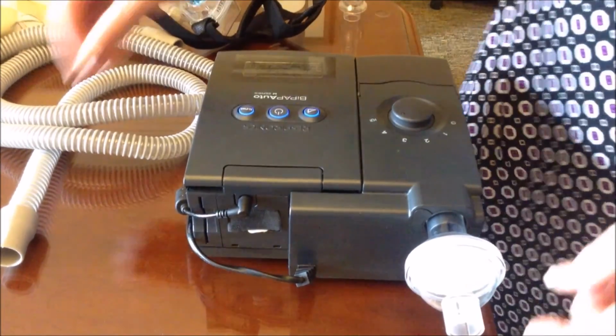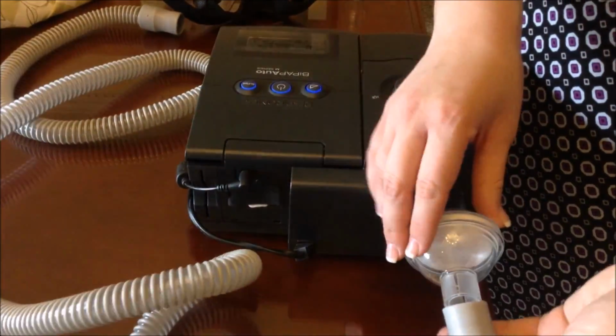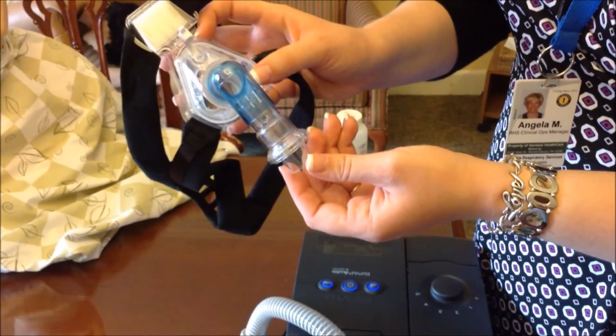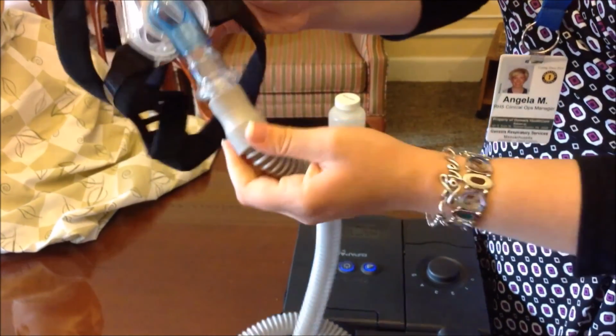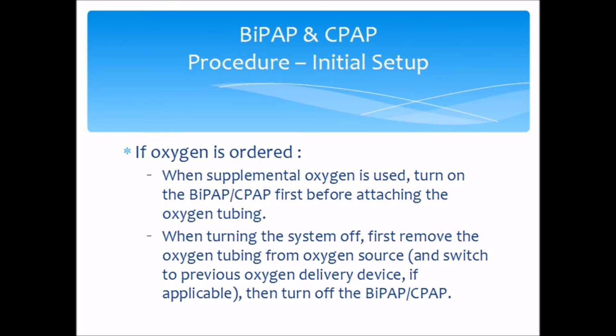Connect the end of the large bore tubing to the outflow of the unit. Connect the other end to the external exhalation valve of the mask. If the mask does not have an external exhalation valve, one needs to be added to the mask. If oxygen is ordered, when supplemental oxygen is used, turn on the Bipap or CPAP machine first, before attaching the oxygen tubing. When turning the system off, first remove the oxygen tubing from the oxygen source, and switch to previous oxygen delivery device if applicable, then turn off the Bipap or CPAP machine.